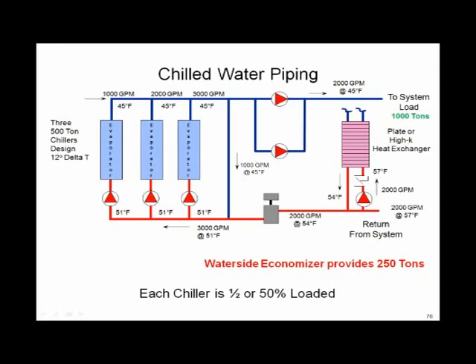This is primary, secondary, just to show you so you can see relationships. Blue is cold supply water, red is return of hot water. Very simple. So in this particular case, I've got a 1,000-ton load going out to the building, 2,000 GPM at 45 degrees. I got a 1,000-ton load. I got 3 chillers online. I got a waterside economizer on the return, and my return temperature to the waterside economizer is 2,000 GPM of 57-degree water. But instead of dumping that 57-degree water back to the chiller plant, I'm going to take it down to 54 with the waterside economizer.